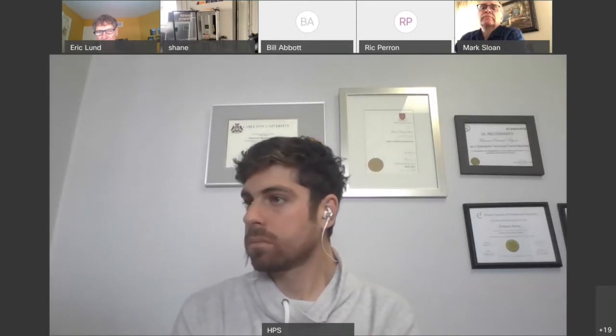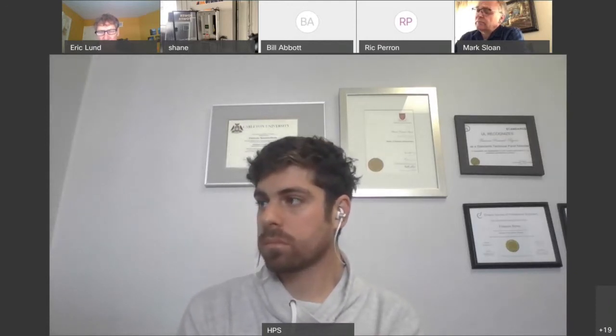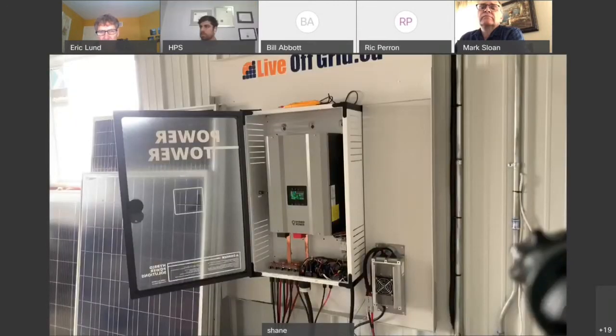Well, the pricing is going to be driven up because of lithium if you're comparing to lead acid. But I'll tell you this: if you had a gel or AGM bank of the same capacity, don't forget that has to be 2.25 times more per kilowatt for a gel or AGM bank. The price per installed system is almost the same because my labor is cut down by about 8 hours on these systems.